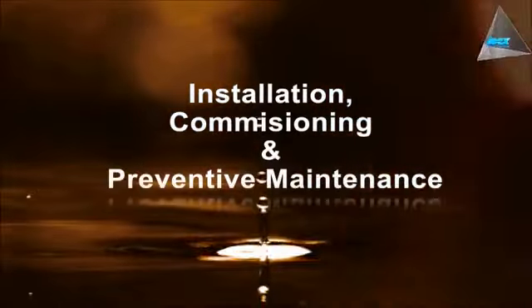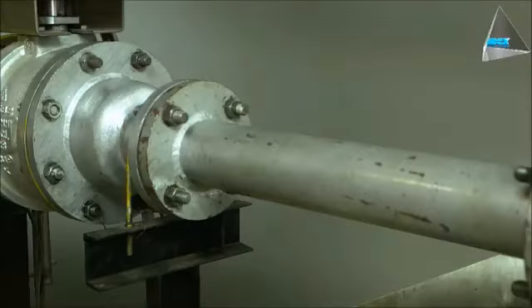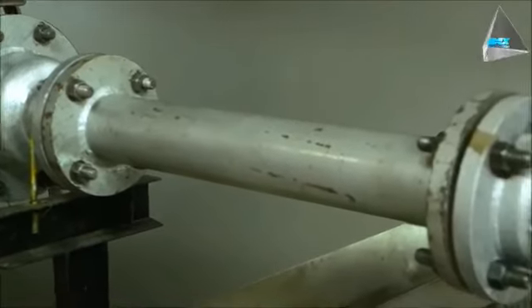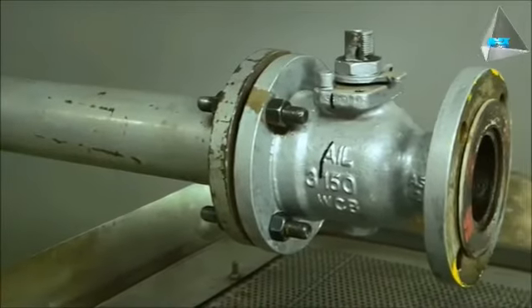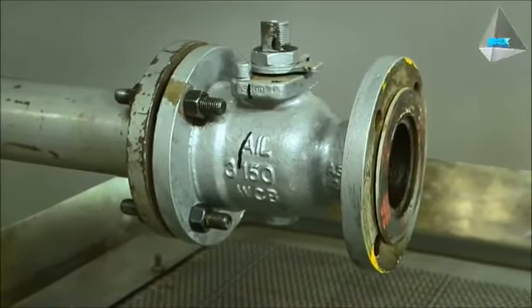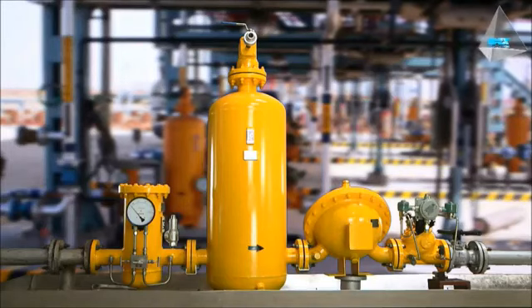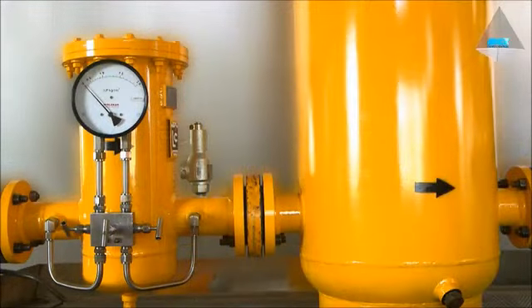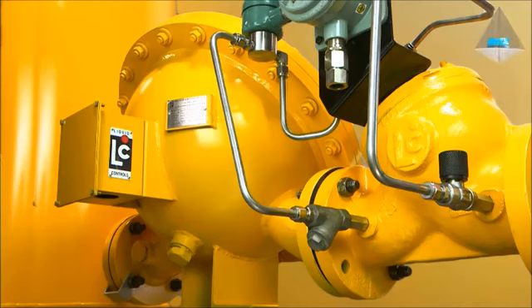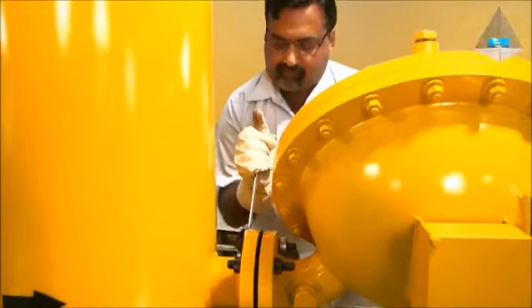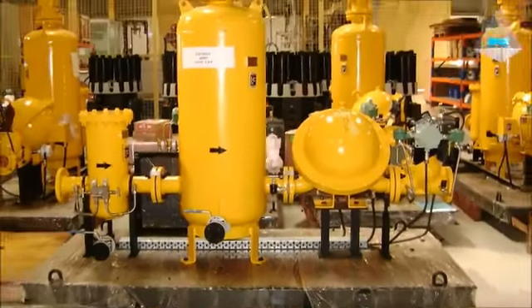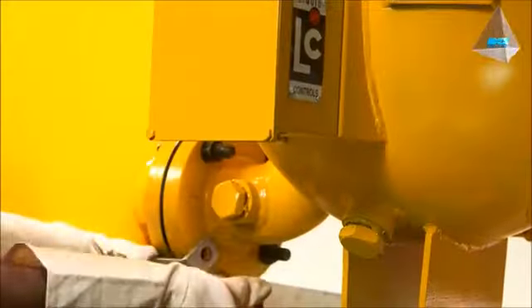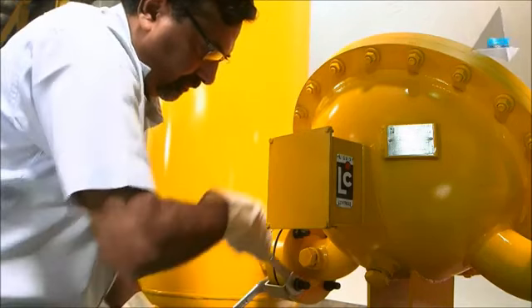Installation, commissioning and maintenance. PD meter installation. The entire piping system should be thoroughly flushed of all debris prior to meter installation with a liquid compatible with the meter construction. The meter installation position should allow for easy access towards any routine service and preventive maintenance. The meter must never hang on the connecting piping. It must always be securely bolted to a platform. Mounting the same on a skid would allow ease of installation. Do not create pipe stress or strain when piping the meter.